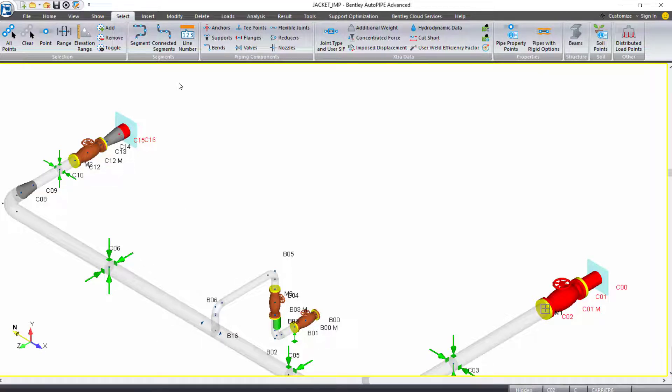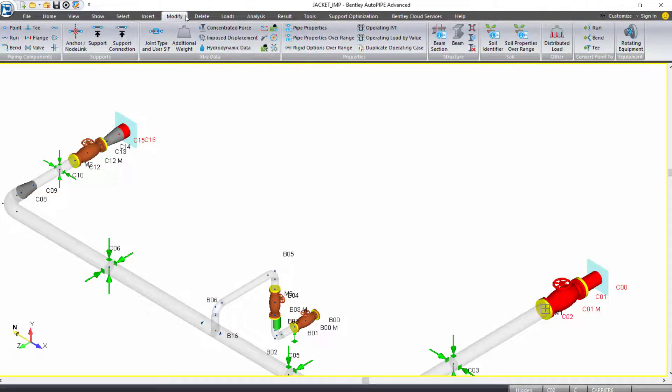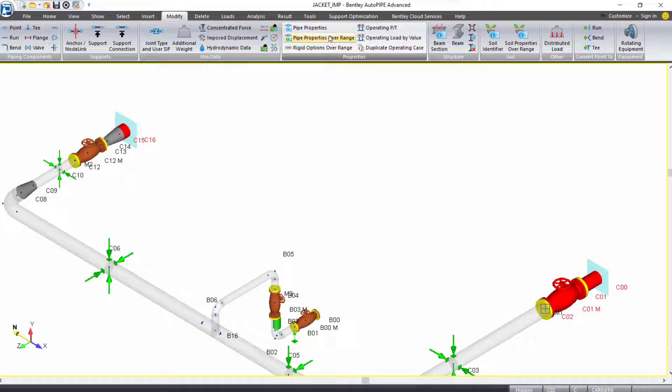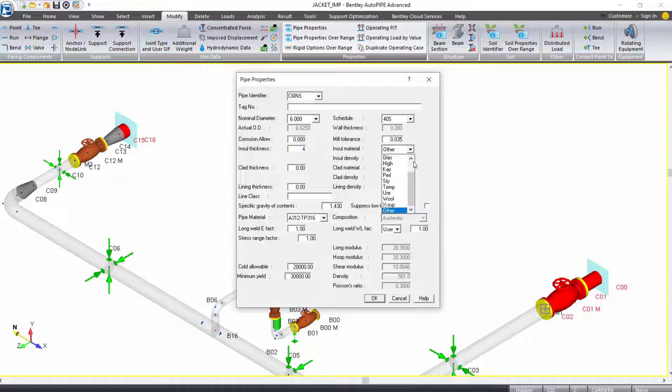I'll come up to my modify ribbon tab. Under the properties grouping, I'll select pipe properties over range. I'll make this pipe identifier C6INS, my six inch carrier pipe with insulation. I'll tab down to my insulation thickness input, and we're going to keep the same insulation. So again, four inches with the material being calcium silicate represented by calc. I can click OK and OK.